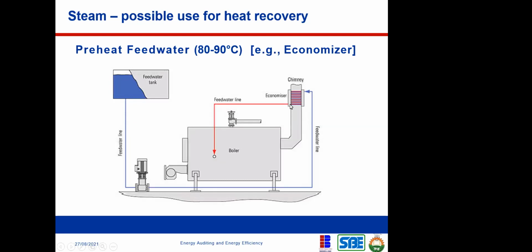So when you recover the heat, you now pass that water into the boiler itself. Okay, so before the water gets into the boiler, the water is already hot, right? So you don't need so much heat to raise it again to 100 degrees centigrade. That's how you save energy. You reduce the amount of heat that you need to heat that water to 100 degrees centigrade. So first of all, you preheat the water using the heat here that would have otherwise gone out.